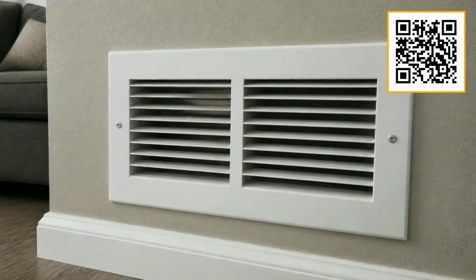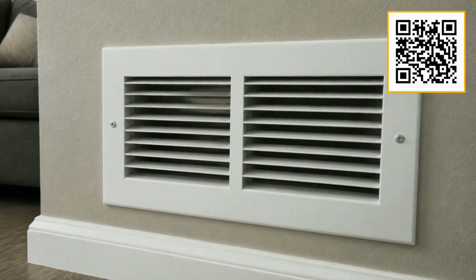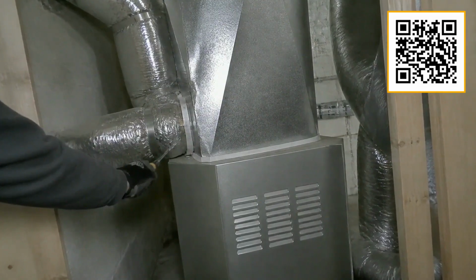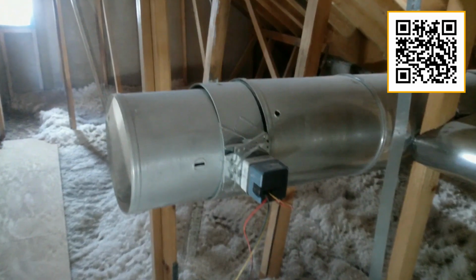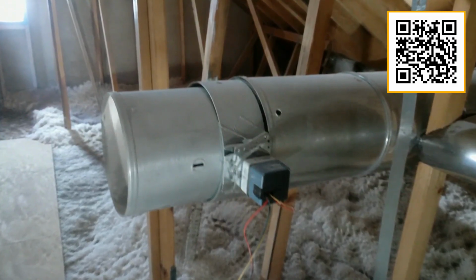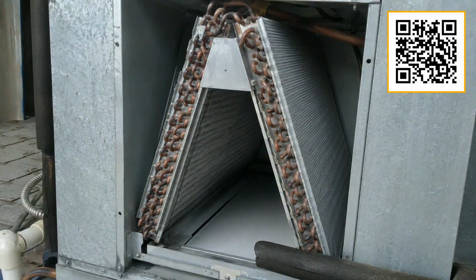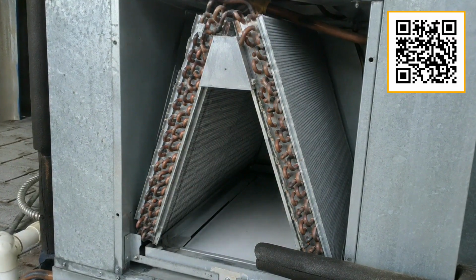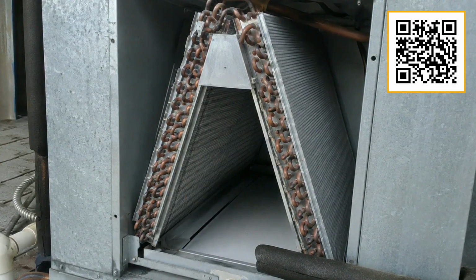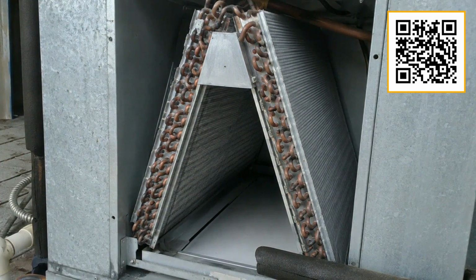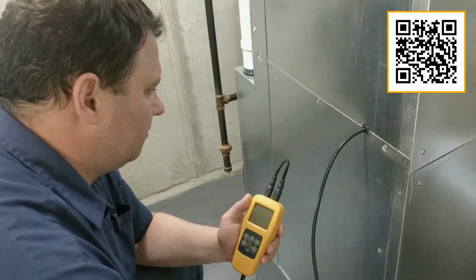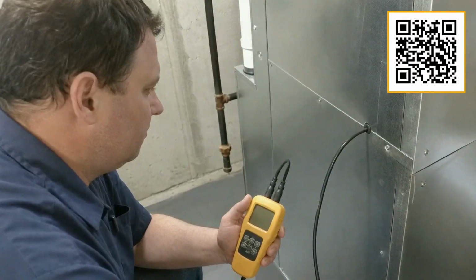So what should you actually do if you want to condition different parts of your home at different levels? The right tool for that job is a zoning system. These use motorized dampers installed inside the ductwork itself, controlled by multiple thermostats, one for each zone you define. When one zone reaches its target temperature, its damper partially closes in a controlled, engineered way that the system accounts for. The blower and the controls work together to keep static pressure within safe limits. It is not a weekend project, and it is not free, but it is the proper engineering solution to the problem. A qualified HVAC technician can tell you whether your existing ductwork can support a zoning setup and give you a realistic number for your home.